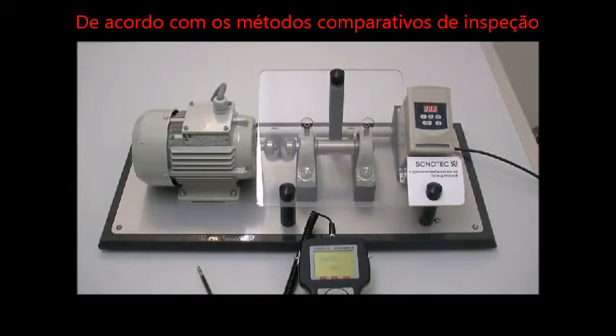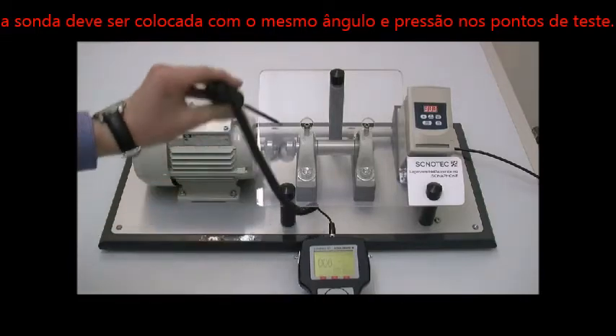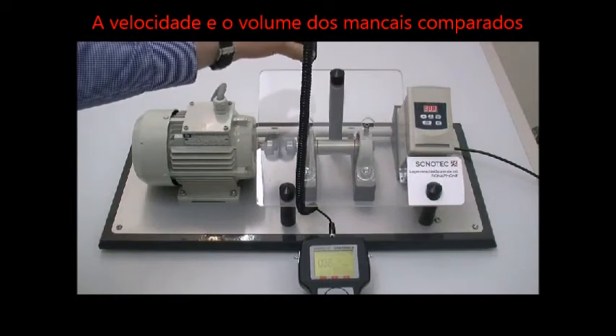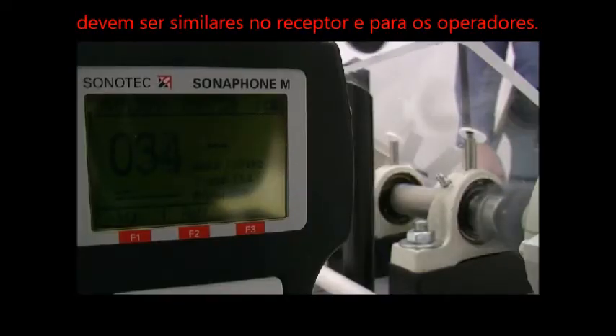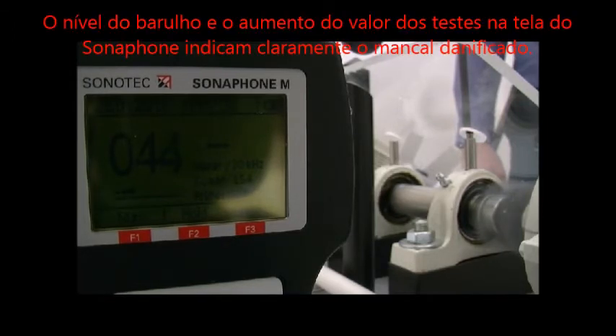According to the comparative inspection method, the probe must be placed at the same angle with equal pressure and on a similar test point. The speed and load of the compared bearings should also be similar in order to receive unbiased test results. The noise level and the increased test value on the Sonaphone display clearly indicate the damaged bearing.